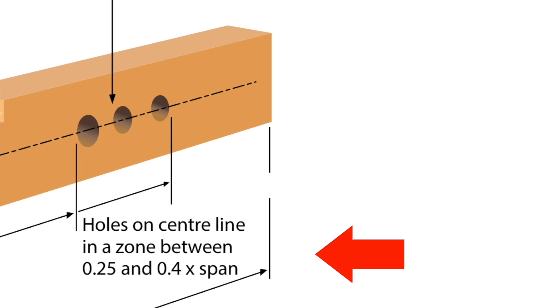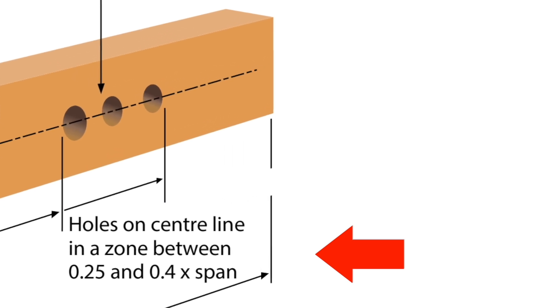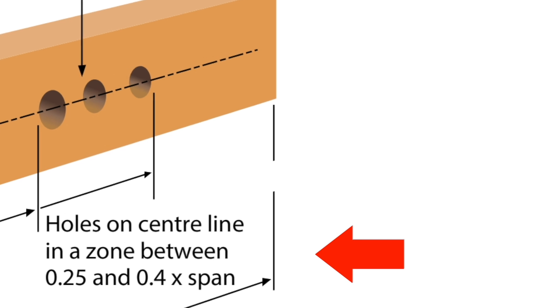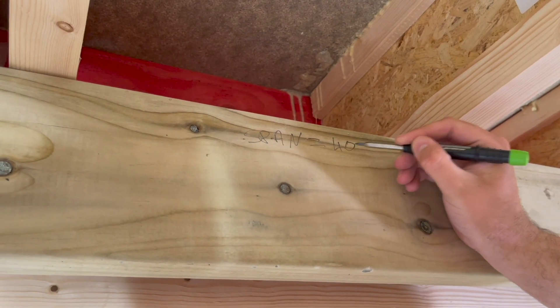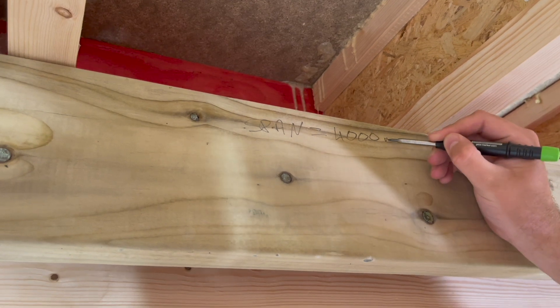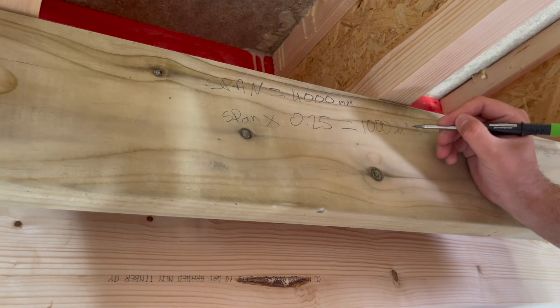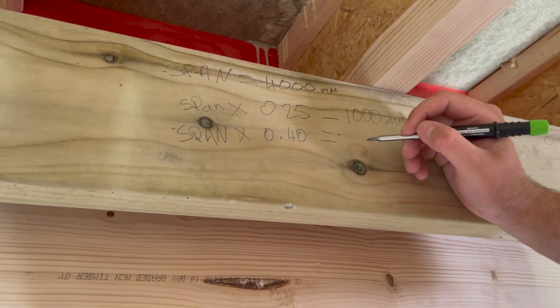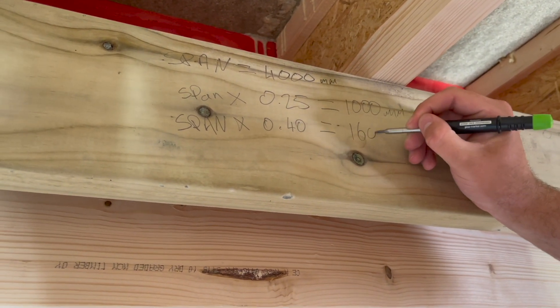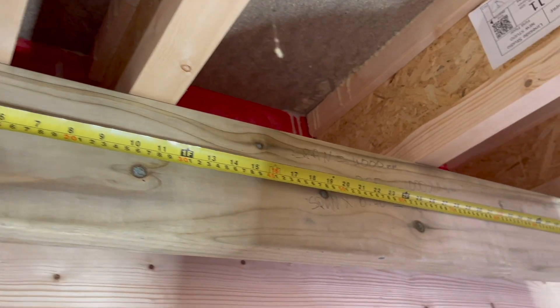And finally D: located between 0.25 and 0.4 times the span from the support. It is important to note that this measurement applies to either side of the joist, and as an electrician this could mean that before we lift that board we might want to get our tape measure out and do some quick measurements. Assuming a span of 4000mm, 0.25 times 4000 equals 1000mm and 0.4 times 4000 equals 1600mm. Effectively that leaves us with a zone of 600mm starting exactly one metre from the left or right support where we are allowed to drill our holes.